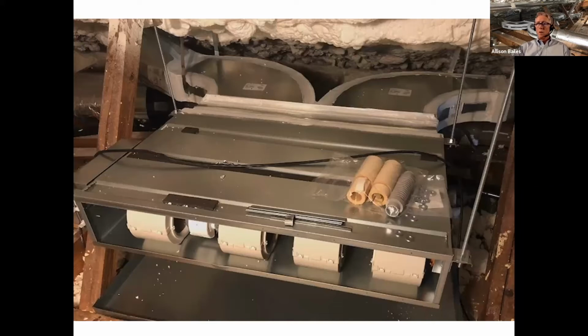So in residential systems, it starts with the blower. You pick a blower, and then you design your duct system around that. That's the opposite of commercial systems. In a commercial system, you design your duct system, and then you figure out what blower you need to go with it. But in residential, you pick the blower first and then design the duct system. So the juggling happens by looking at the other factors.